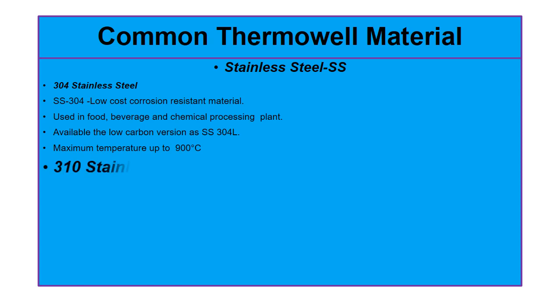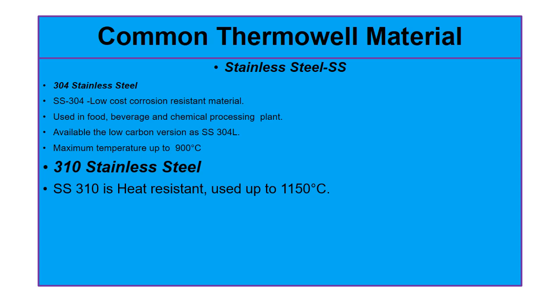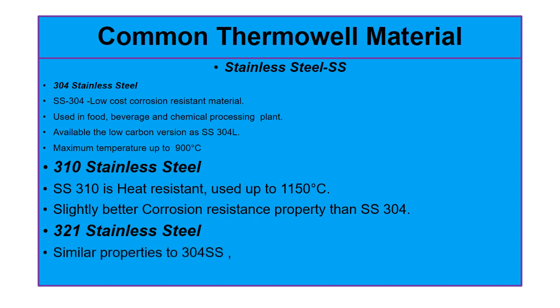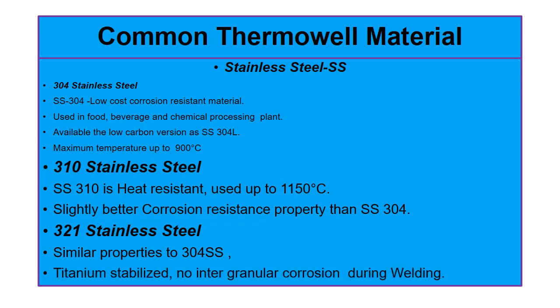Grade 310 stainless steel: SS 310 is heat resistant and can be used up to 1150 degrees centigrade. The corrosion resistant property of SS 310 is slightly better than SS 304. Grade 321 SS: SS 321 has similar properties as SS 304, except this grade is titanium stabilized, which prevents intergranular corrosion during welding.